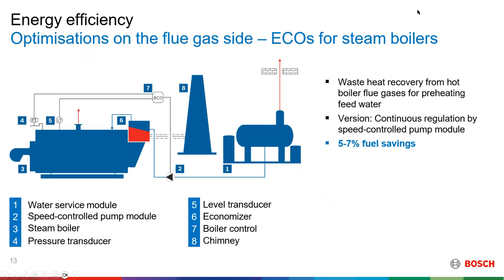For some topics, I'm sure Nick has mentioned on previous trainings, water will be moving from the feed water tank at a temperature of around 85 to 90 for partial deaeration, 103 to 105 for full deaeration, and into the economizer. Then from the economizer, you'll have water at a temperature of 130. Then if you're operating a boiler, let's say a 10-ton boiler operating at 10 bar, the temperature of the water inside the boiler will be around 185.